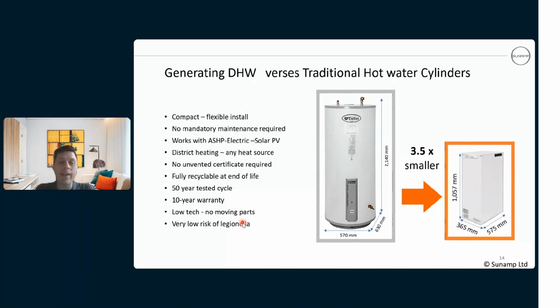We've got very low risk of Legionella there, but we've got less than 15 litres in this cylinder, that's the cylinder in this heat battery. Because of that, we don't have to comply with Legionella, and plus with the heat requirements that we have, the heat that gets generated within the unit is taking us above 55, so there's no Legionella cycle required for that unit.